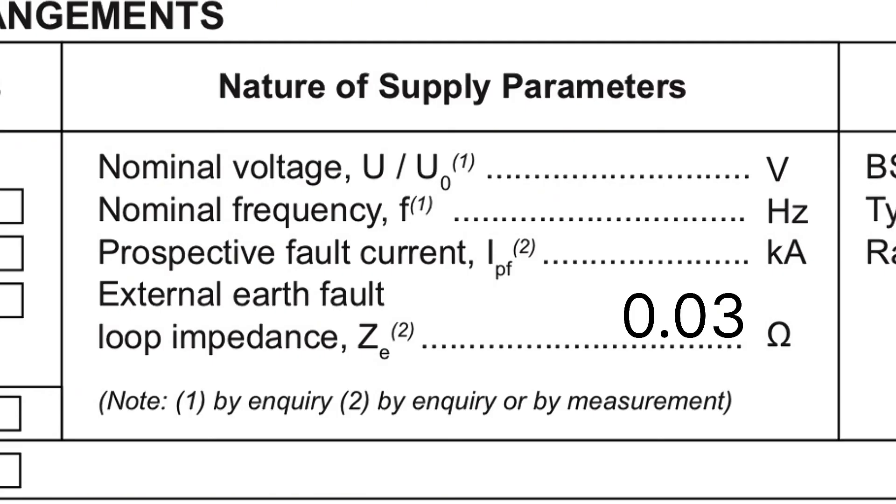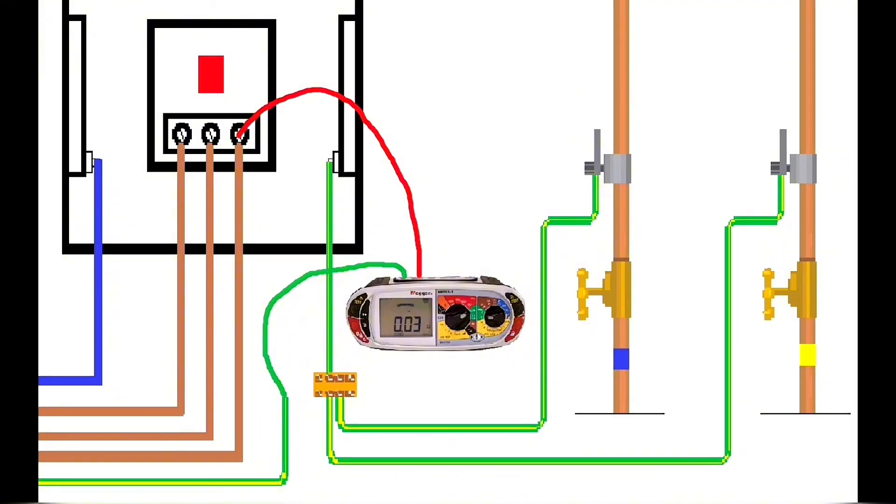That's my Ze value, my external earth fault loop impedance of this distribution board. You note all parallel earth paths are removed because the earthing conductor was removed from the MET.